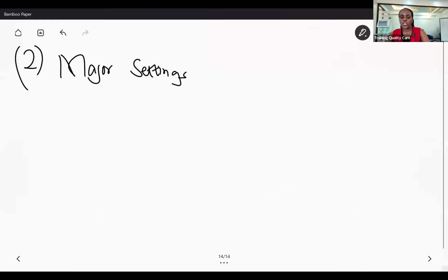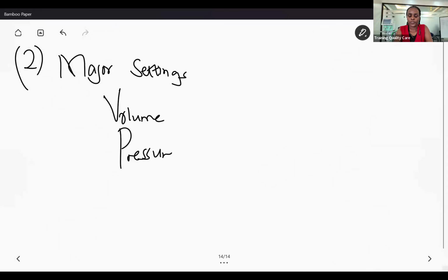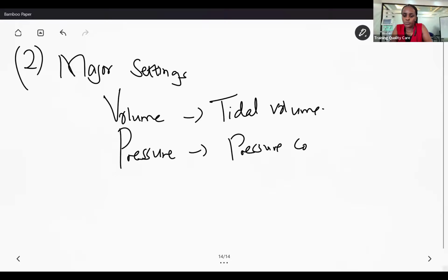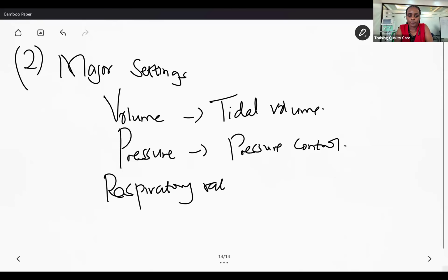For the major settings, now you want to think what you want to cycle. Cycle is what you want at the end of that inspiration. What do you want delivered? Is it volume or is it pressure? So for the major settings, if you decide it's volume, what you're going to set is the tidal volume. If you decide to cycle pressure, what you're going to set is the pressure control. The other thing on major settings is the respiratory rate. So for this one, it's either volume or pressure. You have to think about the respiratory rate.